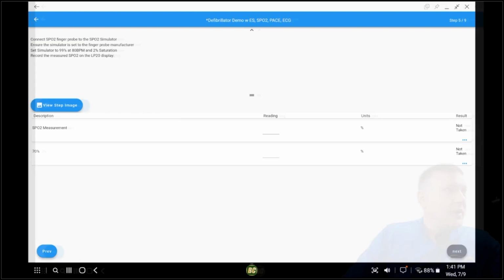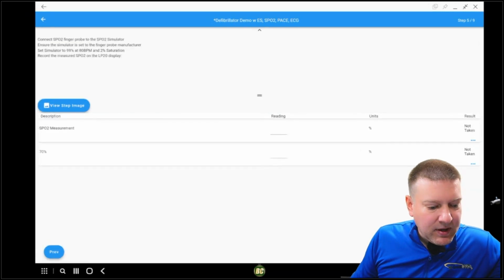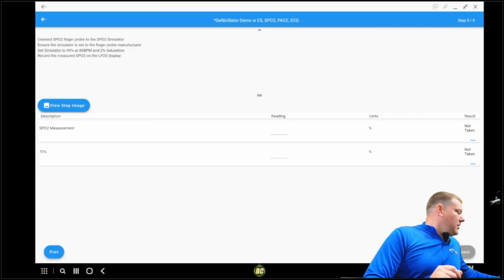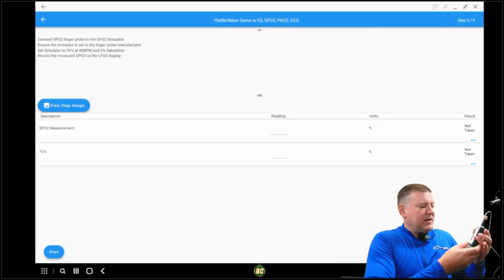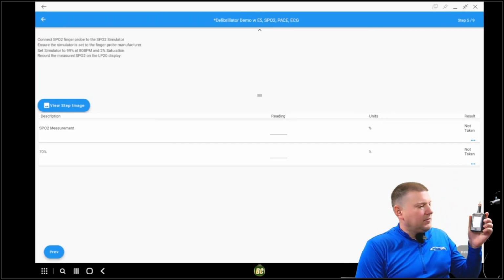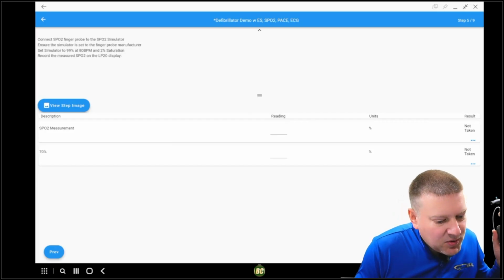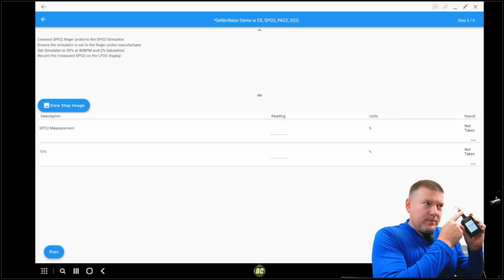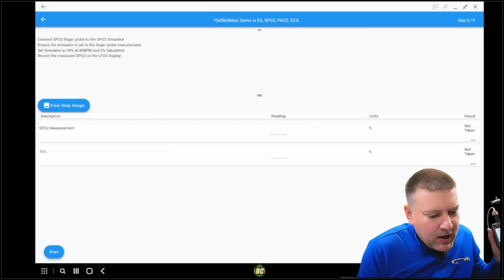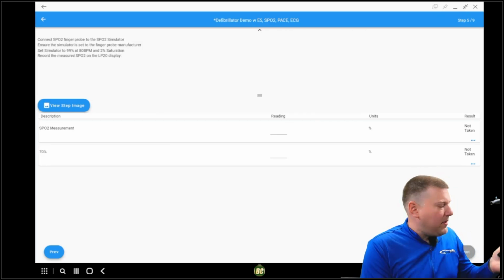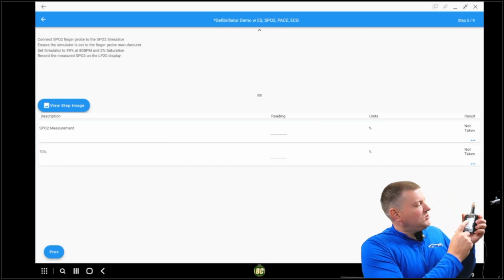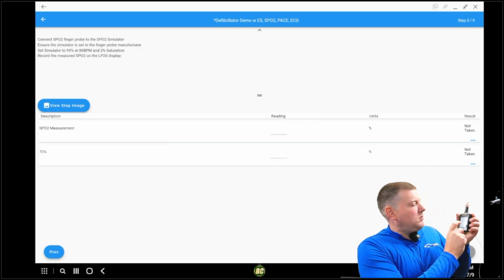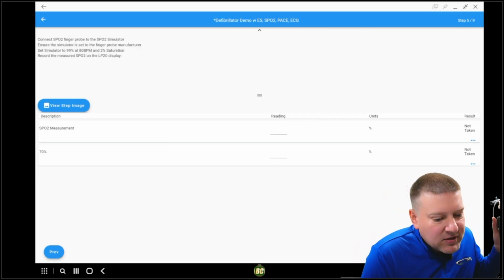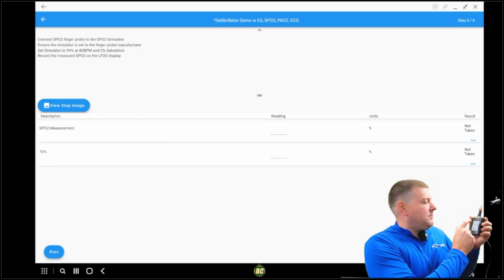And on this step right here, it's saying the SpO2. So I take my handy dandy FSX and it gives me specific instructions on what to do. It says connect the SpO2, which you can see I have a disposable on there. Ensure the simulator is set to finger probe manufacturer. So this is where I'm going to set it to Masimo. And it says set simulator to 99%.